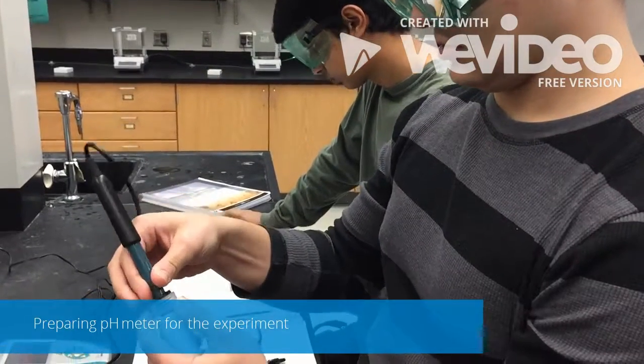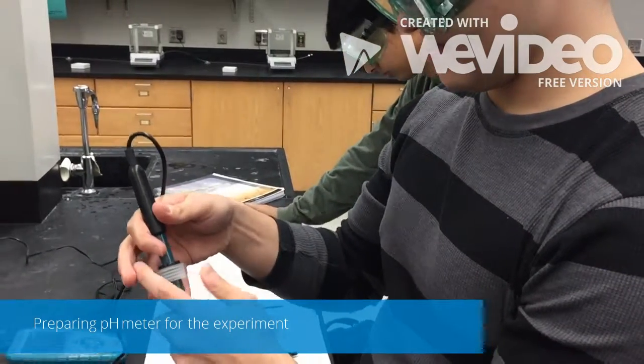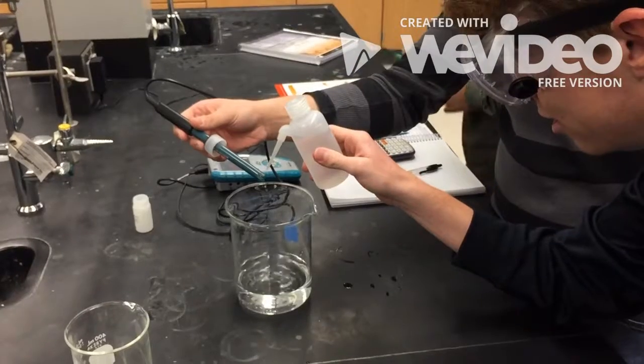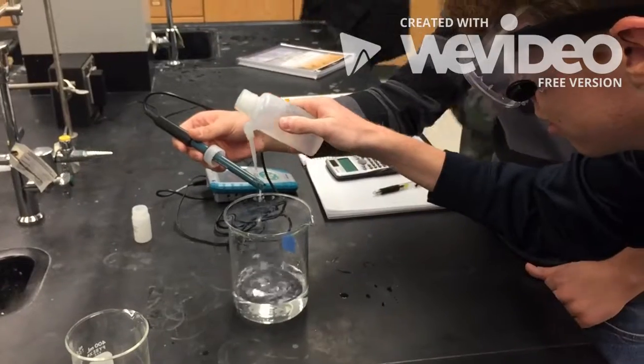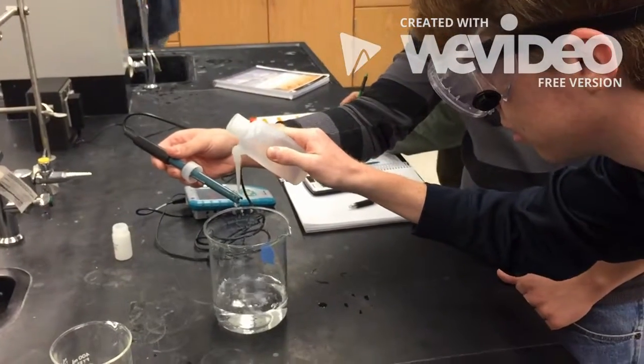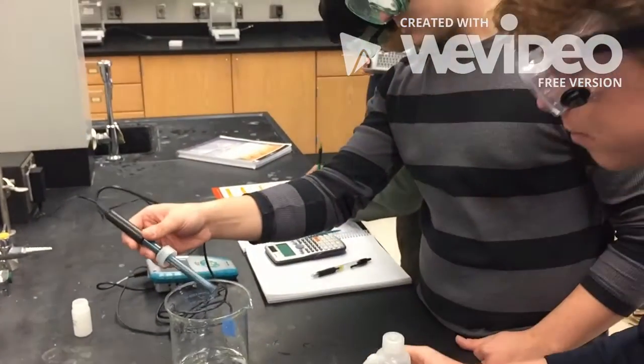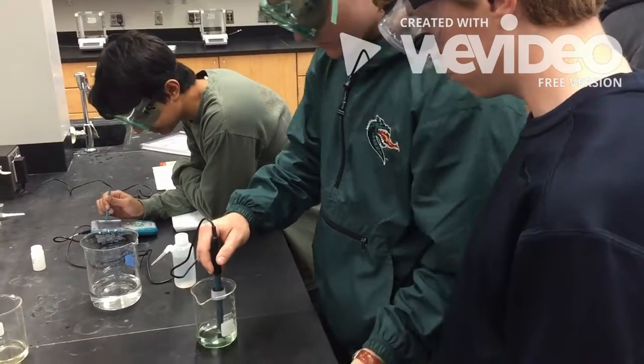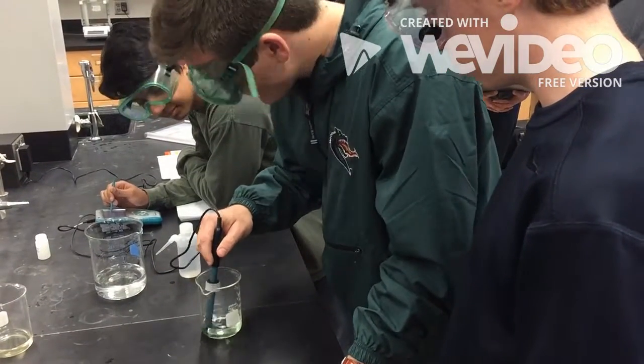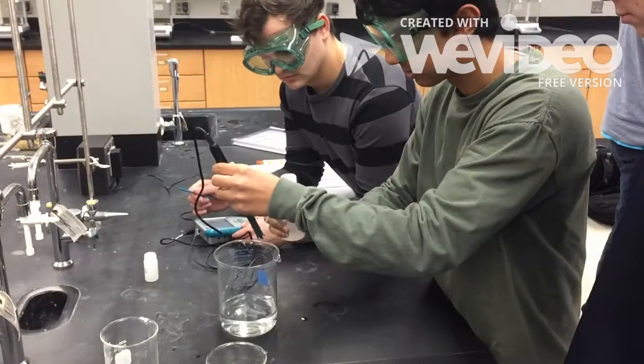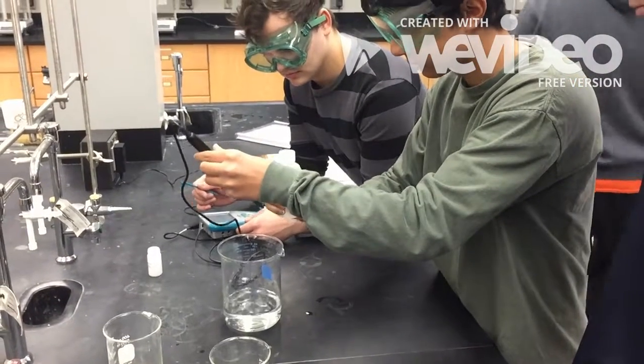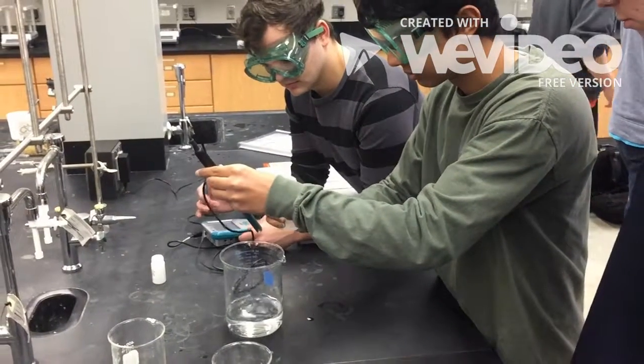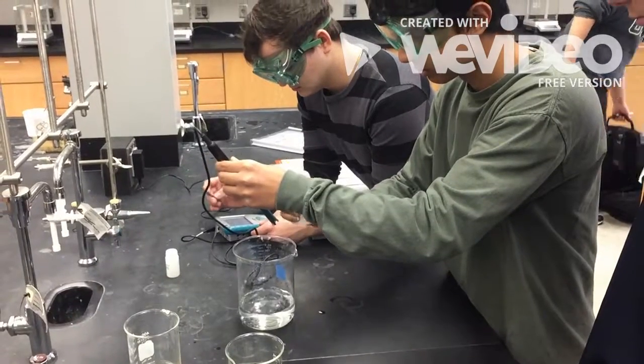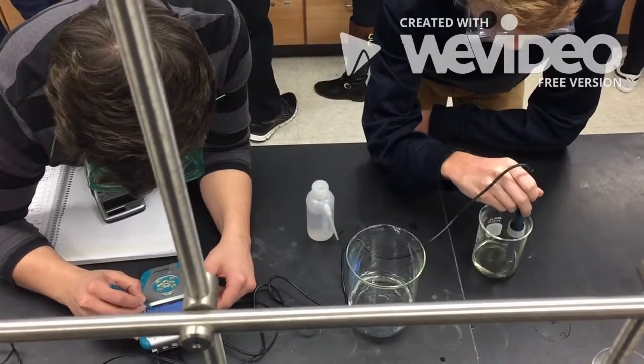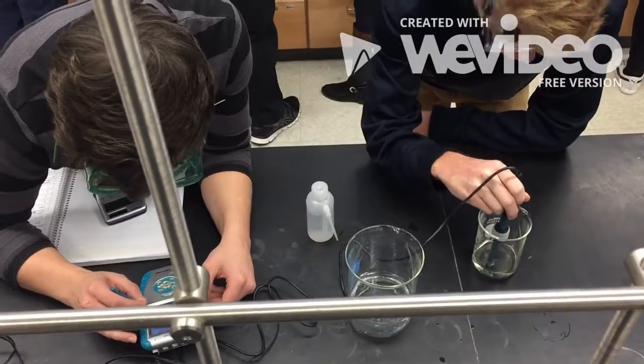Before we begin our experiment, we must prepare our pH meter for use. The first step in preparation of the pH meter is to simply rinse off the pH meter with water. Next, we place the meter in the pH 7 buffer to calibrate it. We will rinse it again after calibrating with the pH 7 so that we can calibrate it with a pH 4 buffer as well. Then, in the final step of preparation of our pH meter, we will calibrate it in the pH 4 buffer.